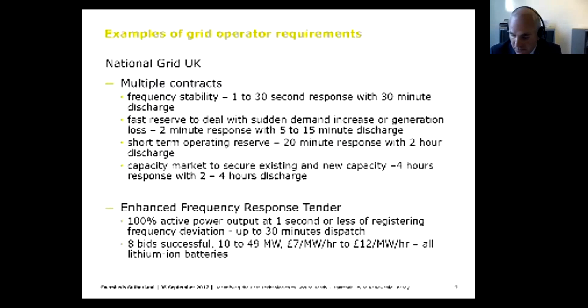Recently in the UK there was a tender in 2015, with results announced last year, called the enhanced frequency response tender. The requirement was 100% of active power output within 1 second or less of a change in frequency deviation, with up to 30 minutes dispatch. There were multiple bids for up to 200 megawatts. 8 bids were successful, ranging in capacity from 10 to 49 megawatts, with prices ranging from 7 to 12 pounds per megawatt per hour, depending on the size of the facility. All the technologies proposed in that case were lithium-ion batteries.